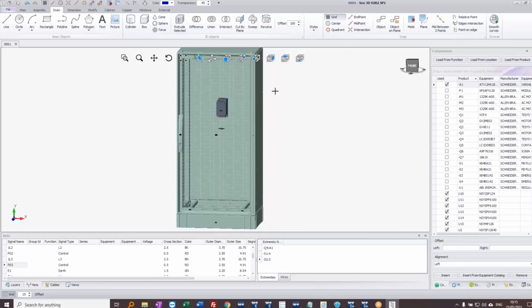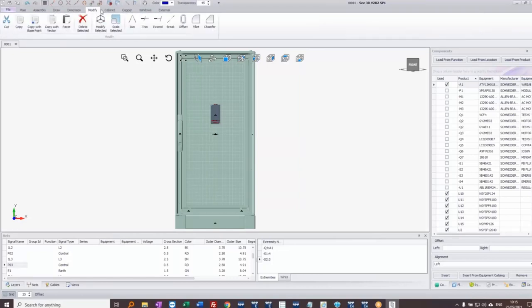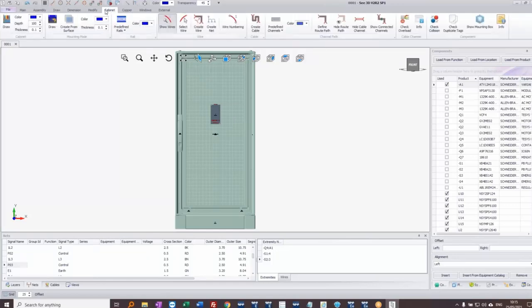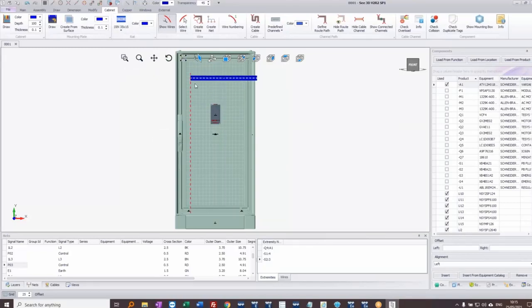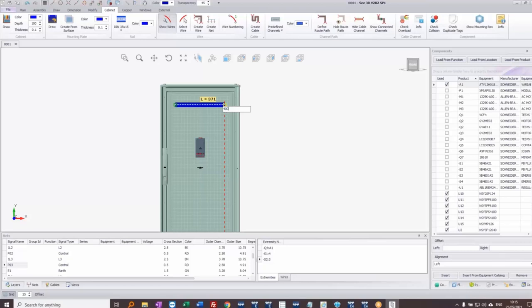SEE Electrical 3D Panel is best suited for bringing in models that someone else has already created and quickly adding intelligence to them. We have dimensions, modification of objects, and under Cabinet we have additional elements. I'll go to predefined rails, click on a DIN rail, and it appears on my cursor. I drop it near the top — there's a handle on the right to change the length. I hit the spacebar to enter a specific value and type 400mm.